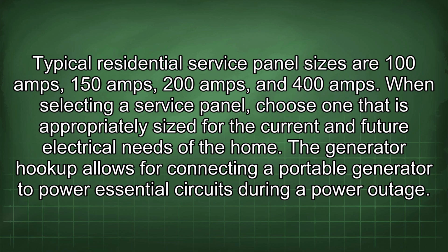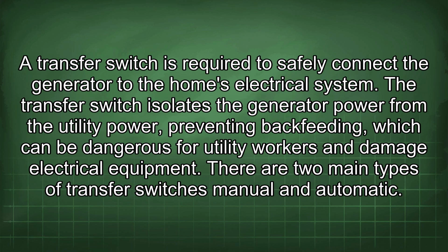home. The generator hookup allows for connecting a portable generator to power essential circuits during a power outage. A transfer switch is required to safely connect the generator to the home's electrical system. The transfer switch isolates the generator power from the utility power, preventing backfeeding, which can be dangerous for utility workers and damage electrical equipment. There are two main types of transfer switches: manual and automatic.